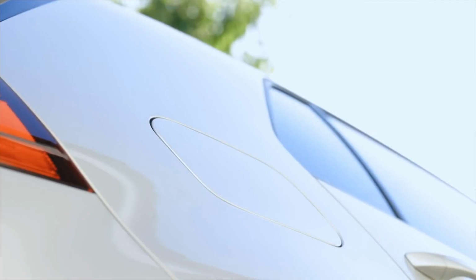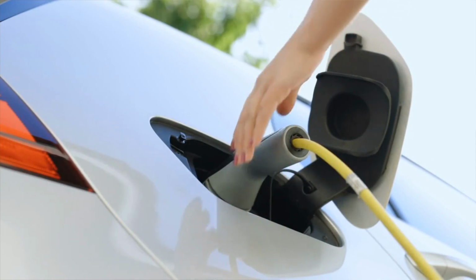But is running an air conditioner in my home and charging an EV different, or similar? There is a lot of difference. When we set a particular temperature on an air conditioner, it meets that level and cuts off, gives some cooling time, and then starts again - a start-stop mechanism where that loading condition never hammers the system. Whereas EV charging continuously takes 6 to 8 hours of continuous rated power, and this loads the system. So where there are weak points and joints and loose connections, it leads to temperature growth and consequent problems.